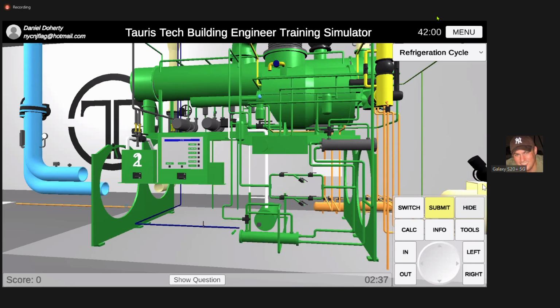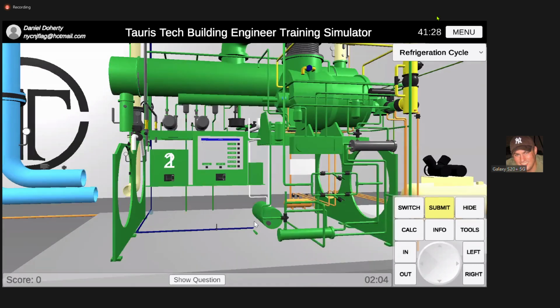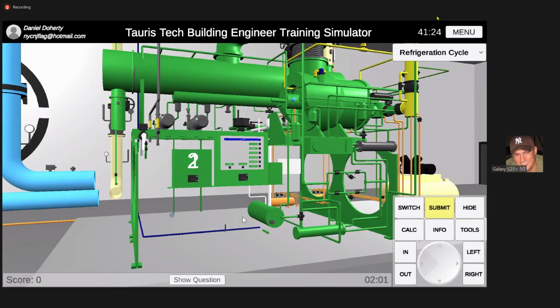So then it's the same thing as a recip. You got a high side and a low side. The high side starts at the compressor. Here it's a little different because it's a centrifugal. So your low side is at your suction line, goes through the guide vanes, and after it passes the guide vanes is where it changes from low to high. So now the motor's spinning, and it's throwing the refrigerant against the wall with centrifugal force. And that's pressurizing the refrigerant. Okay, and then the other side would be your orifice plate. Your orifice plate changes it from a high pressure to a low pressure. Right, okay?